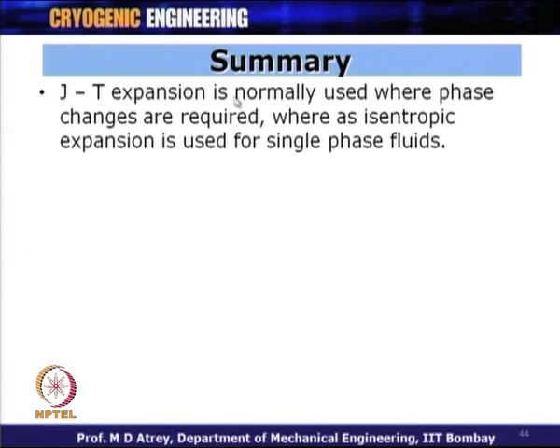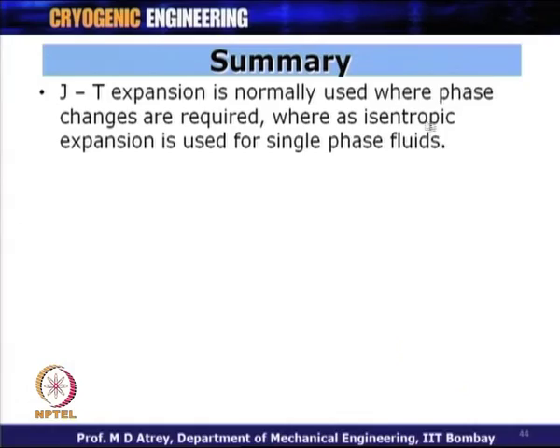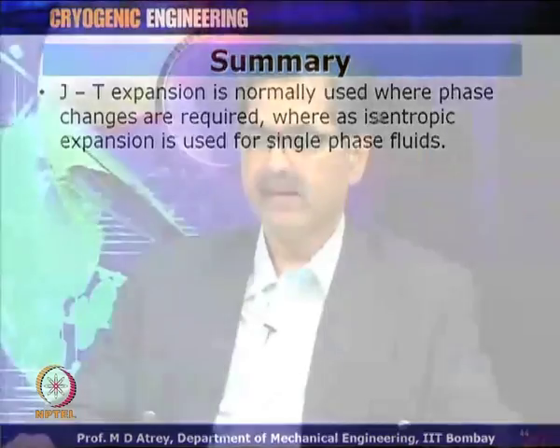JT expansion is normally used where phase changes are required, whereas isentropic expansion is used for single-phase fluids. JT expansion prefers real gas behavior and phase changes, while isentropic expansion using turbo or reciprocating expanders should use single-phase fluid — two-phase fluid can cause problems for these devices.